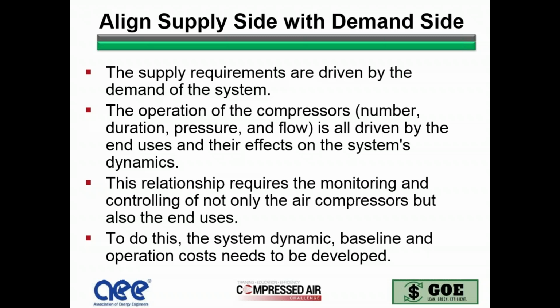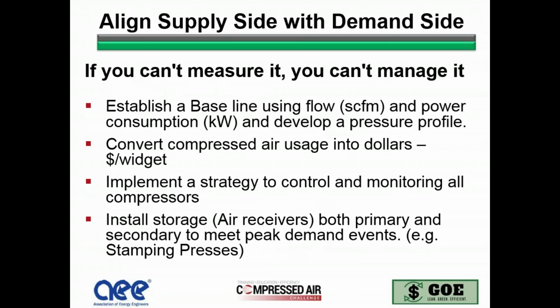So to do this, you want to establish a baseline, remembering that the system is dynamic, and you want to relate this to the operational costs in the system. It needs to be developed so you can understand what those are. Like anything, if you can't measure it, you can't manage it. Again, establishing the baseline is key. Look at flow, which is the output versus the input power in kW, and also develop a pressure profile. These two things allow you to see, one, how efficiently your compressors are working, and two, how dynamic your system is and what's happening in that system.